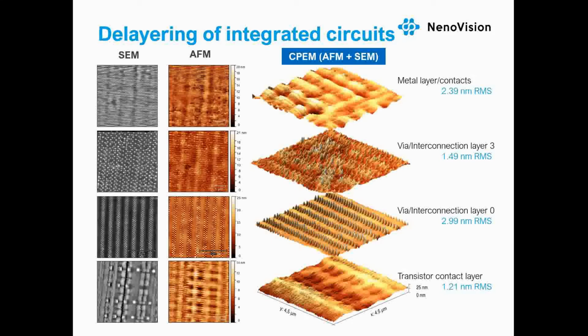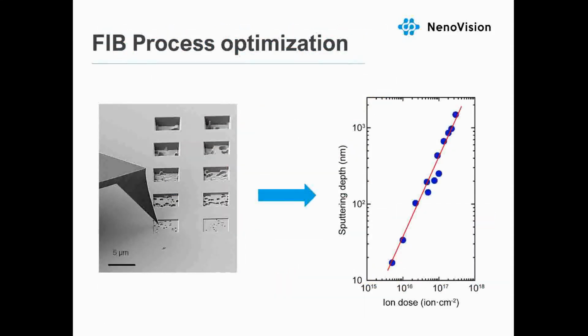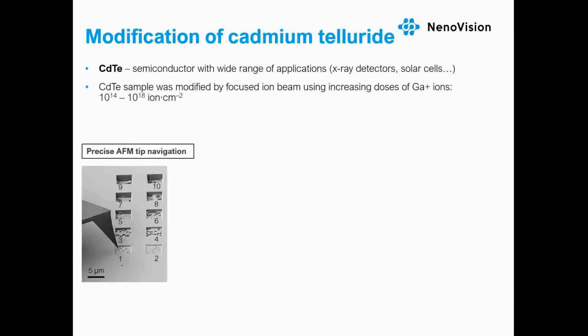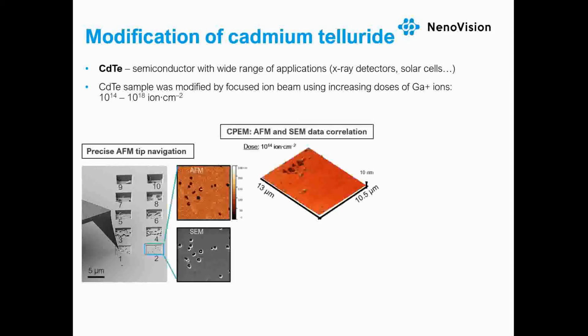This application demonstrates how the combination of AFM with SEM equipped with focused ion beam can be utilized to optimize the focused ion beam milling process. For this purpose, cadmium telluride was sputtered using increasing doses of ions as depicted in the SEM image. Each of the 10 frames was immediately analyzed by AFM and SEM in in-situ conditions. The AFM and SEM data were correlated using CPEM technology and used to optimize the FIB milling process.